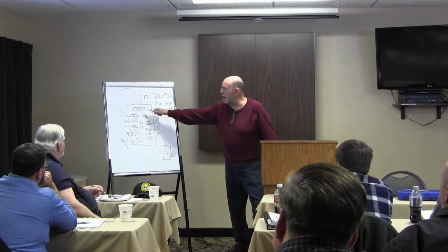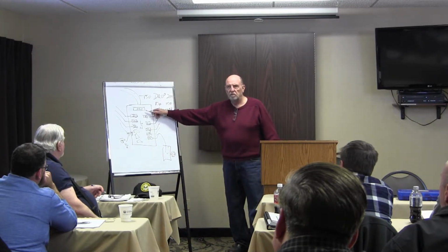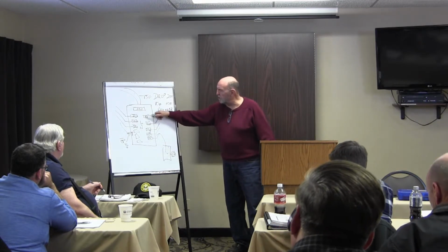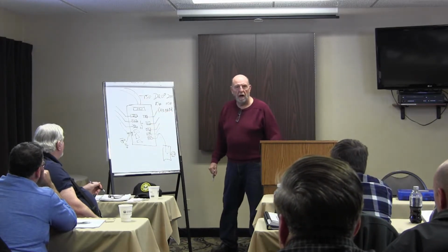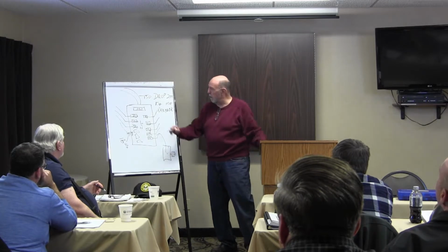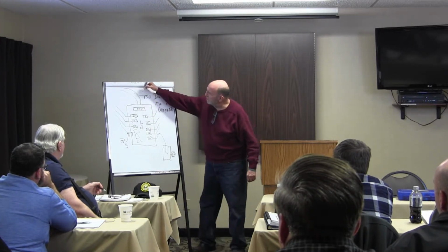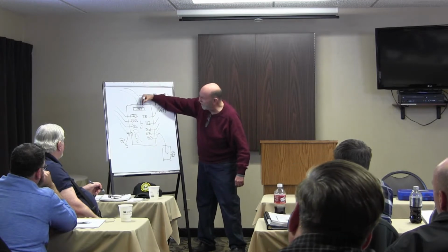So, what's the purpose of that breaker? To keep my bill low? No, so you don't overload it. Overload what? Every circuit here is fine. I'm not worried about the lateral, that's the city's problem. The drop, the drop in the entrance. That's protecting this, which is only rated for 150.